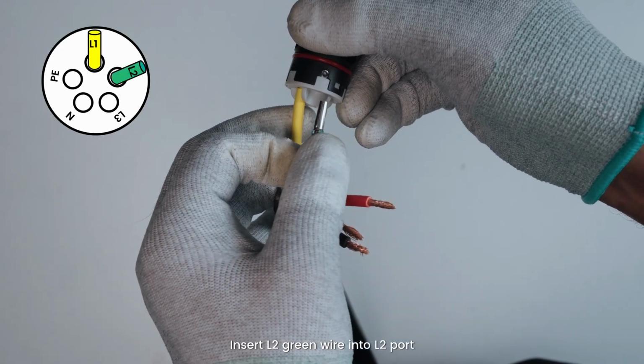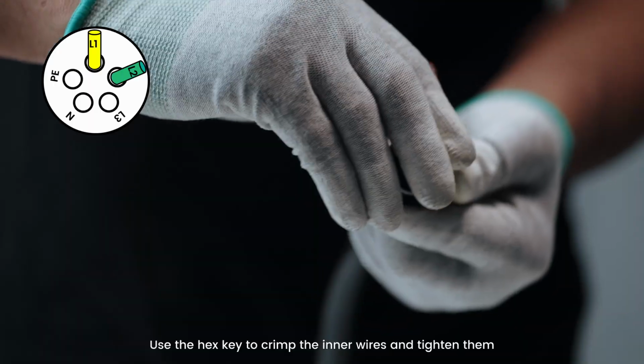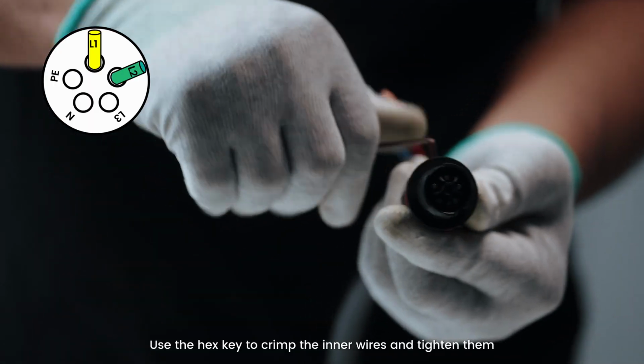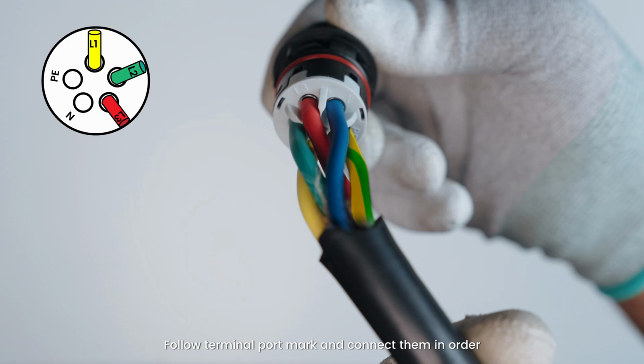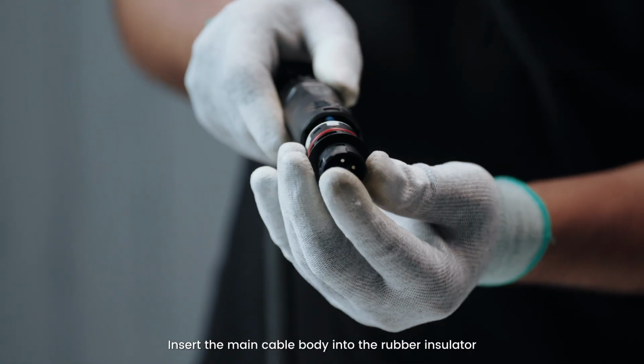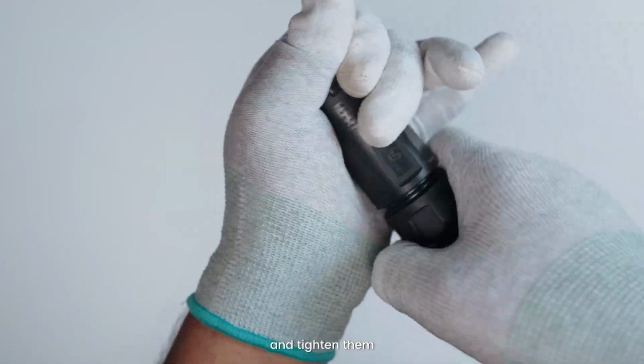Insert L2 green wire into L2 port. Use the hex key to crimp the inner wires and tighten them. Follow terminal port mark and connect them in order. And check the color sequence is correct. Insert the main cable body into the rubber insulator and tighten them.